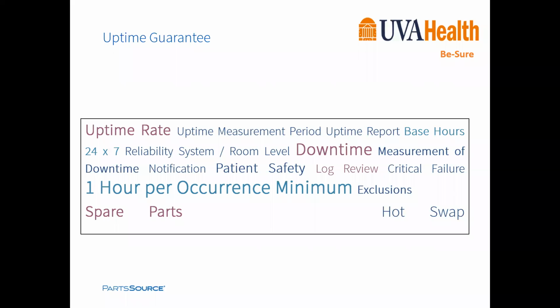We have been creative with vendors in identifying ways of reducing downtime. For example, if a vendor is willing to provide at no charge spare parts that the clinical engineering team can install, whether at 2 o'clock in the afternoon or 2 o'clock in the morning, then downtime is cut down to the actual time from the equipment going down until my team can install the parts and bring it back online. We also look for vendors who have hot-swap capable items or true redundancy.